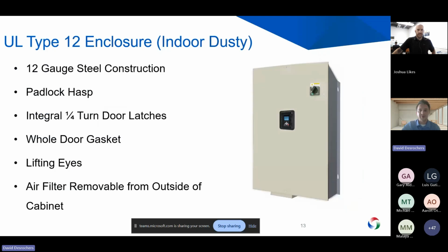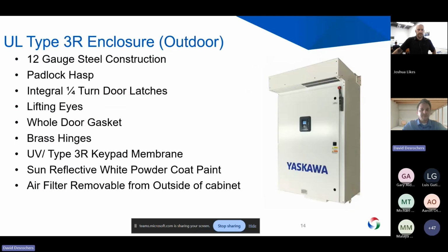Type 12 takes things a bit further. You've got some additional gasketing within the door of the enclosure, and that's going to help mitigate against dusty environments. There's also a small door over the keypad to make that last longer, so you're not getting dust inside it. It is definitely not protective against water to a considerable degree, so I don't want to give that impression. However, dusty environments, a dusty mechanical room indoors, we could say would be a good spot to place these.